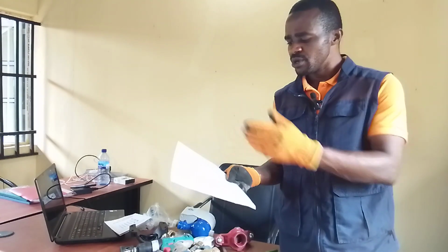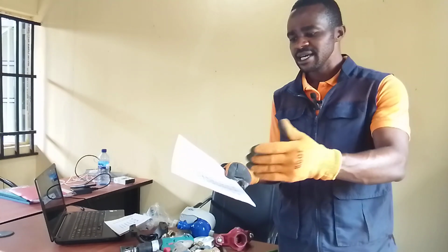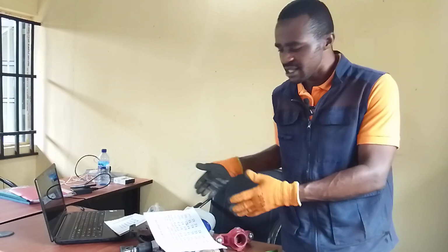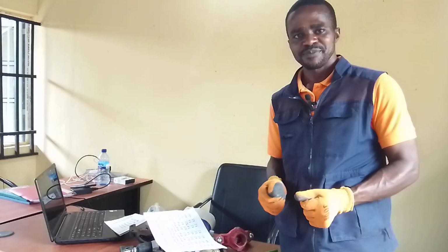For instance, if you go to 2 horsepower pumps, or let's say 3 horsepower pump, when it's between 76 to 90 meters, you'll be using 4 millimeter squared. And today, when we tell some of our professionals that you can actually use 4 millimeter square to install a 3 horsepower pump, they will tell you it's too big, it's too big, without considering that the depth is already above 75 meters, right?